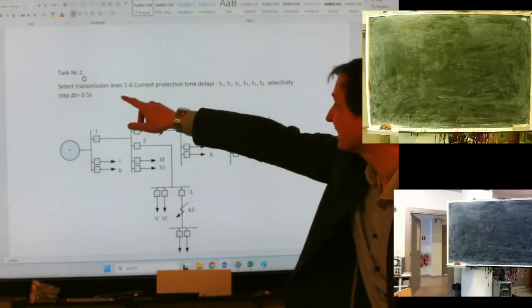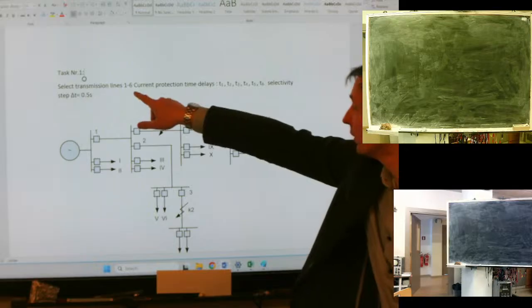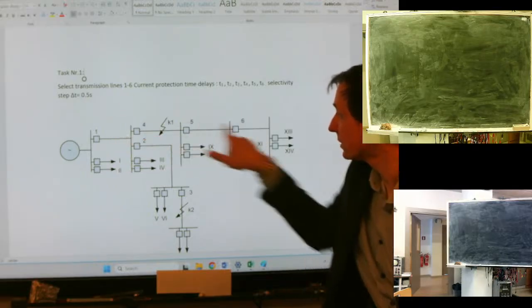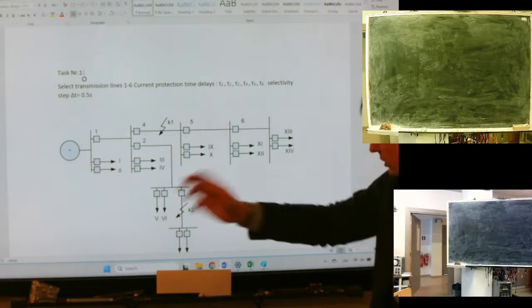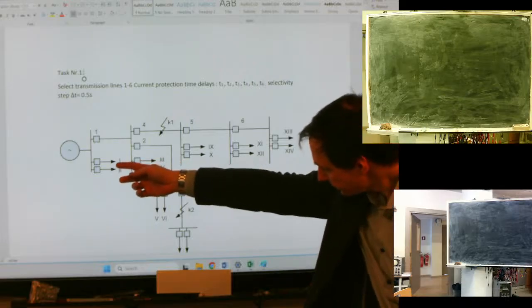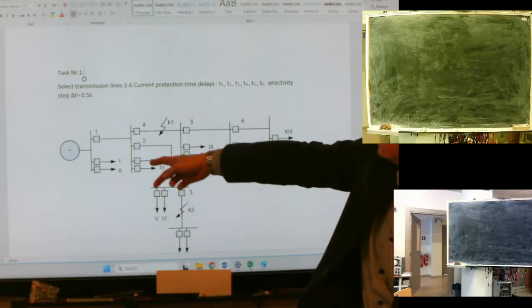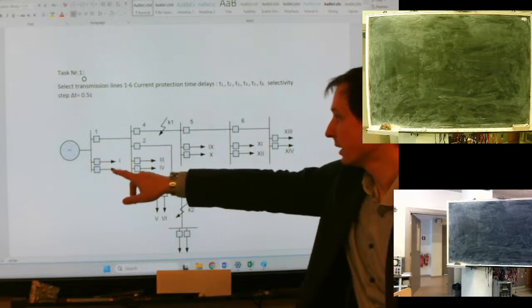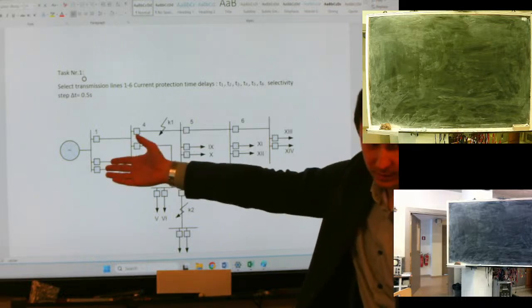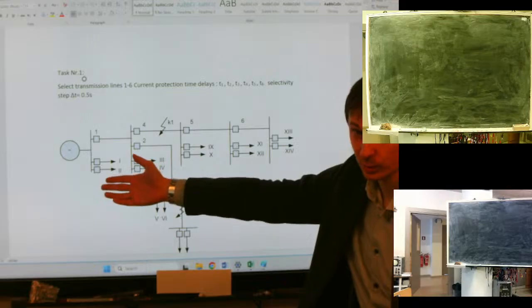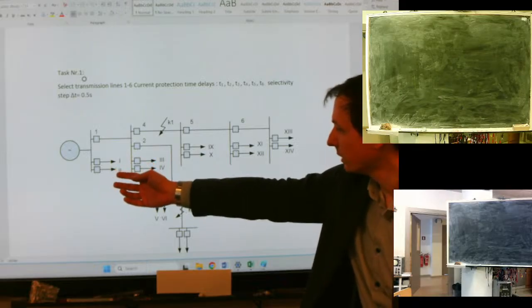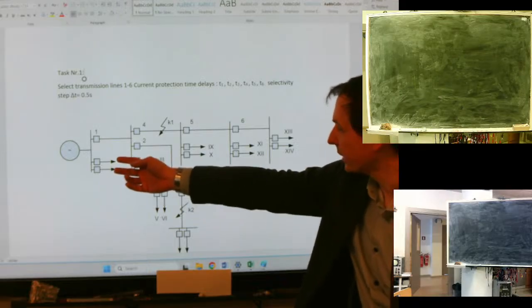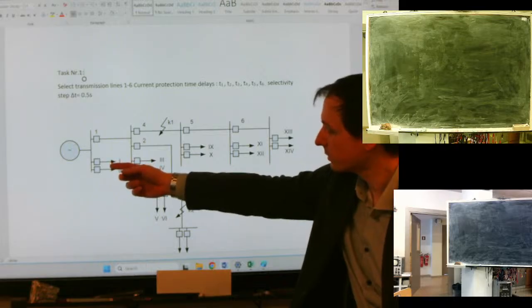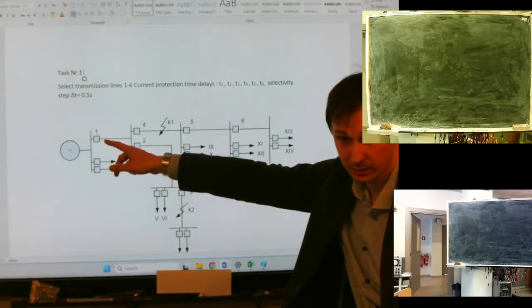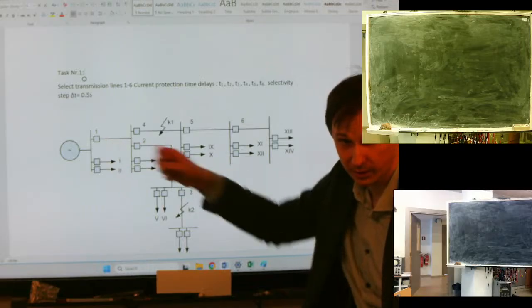As it is written in your task, you need to select only current protection for lines 1 to 6. And you understand that this is also, so this is a load. Yes, it's the last, the only one element in this branch. That means that you don't need to take into account this delay when you're calculating this parallel branch time delay.